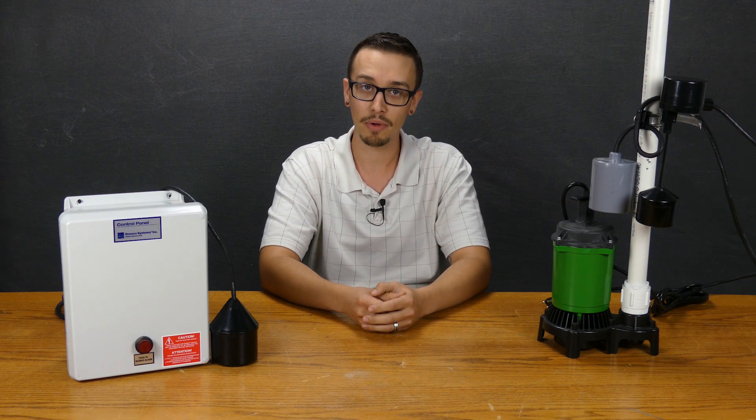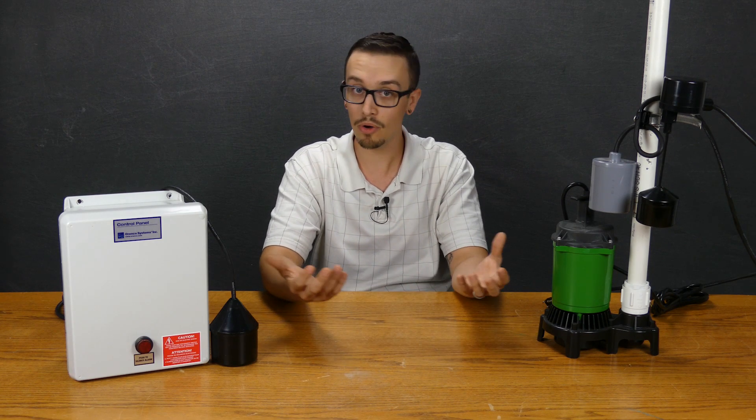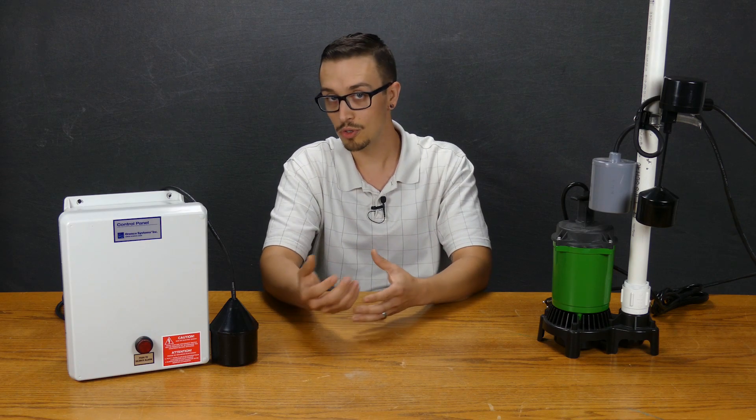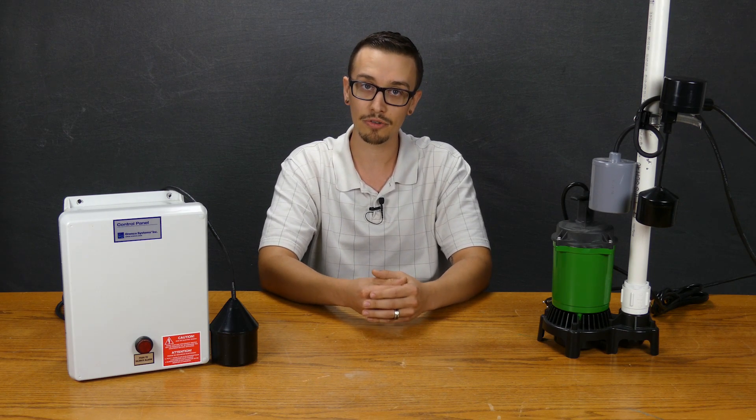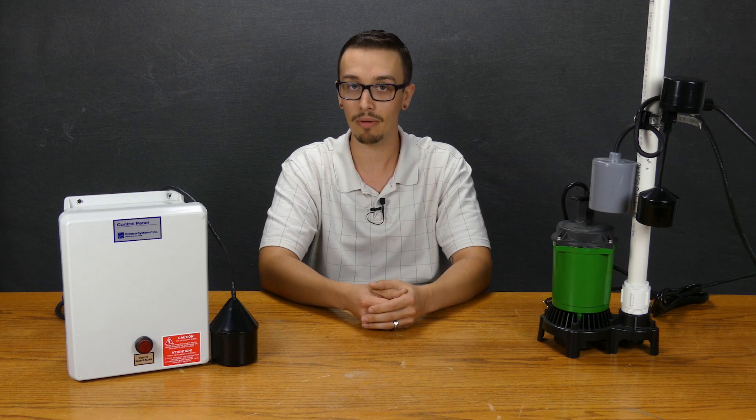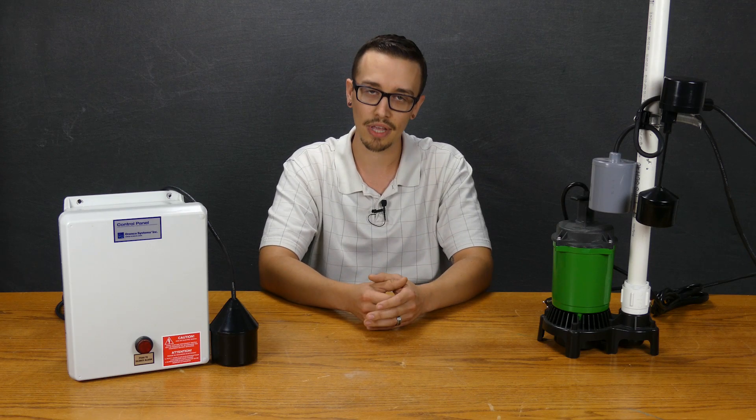So it's definitely in the name when we're talking about the two. A pump switch is intended for the direct control of a pump or a motor really. A control switch has to interface with some sort of a controller in order to actually engage or disengage the pump, and that's typically done through like a contact or some other means such as that.